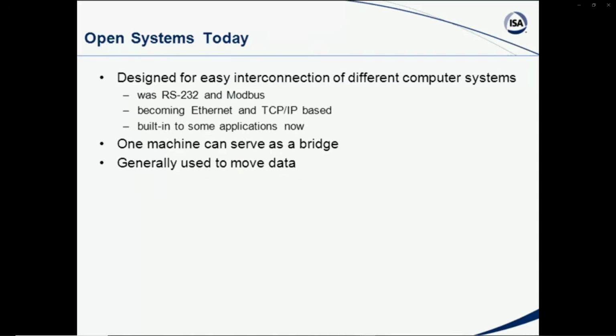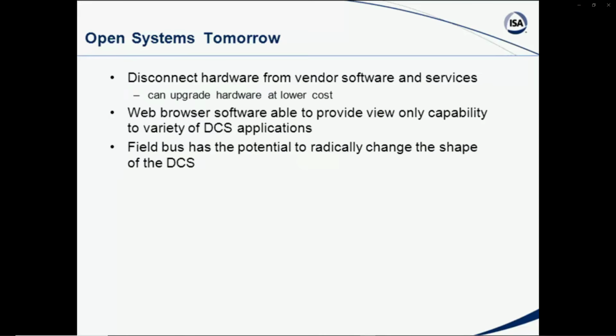Open systems today, they're being designed for easy interconnection, and again using the Ethernet and the TCP/IP based for transmission of data in blocks and chunks back and forth, and using machines as bridges and moving data around. And that's enabled now with equipment being approved to be used with a certain Fieldbus system, and this type of communication has greatly opened up how business is being done today. Of course, we're moving even further all the time.